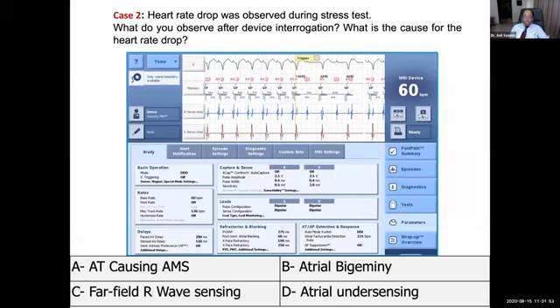Excellent. So most of you have correctly diagnosed it as a far field R wave sensing. Dr. Ma beautifully showed how the ventricular signal can sometimes be sensed in the atrial signal. So we can focus our attention on the atrial sense channel, and we can see that there are two spikes. Now at a lower rate, it may not matter that much, but as the rate increases and the count doubles, it may reach the tachycardia detection rate. And as soon as it reaches the tachycardia detection rate, the patient will have an automatic mode switch.